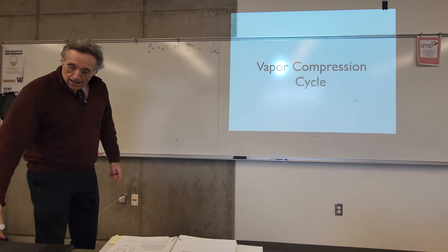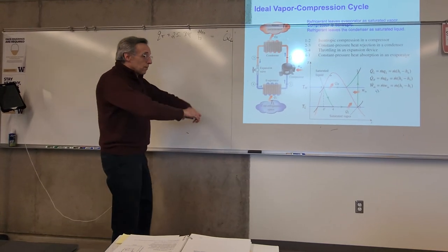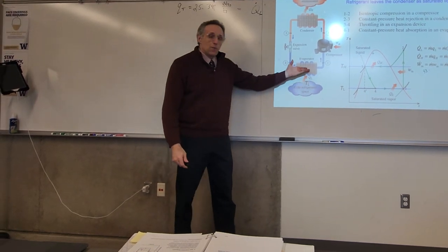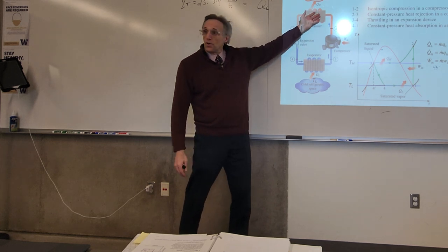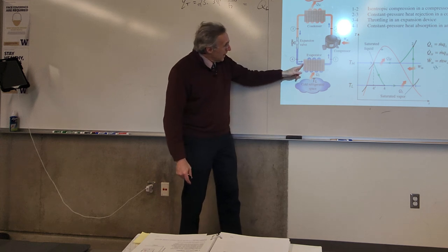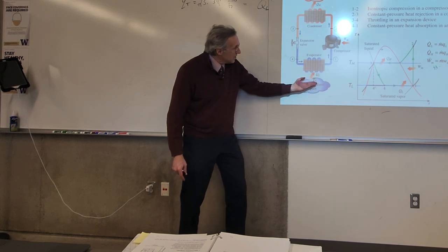And if we look at vapor compression, you open up the black box in the middle of that diagram we just saw, and this is what it looks like. This is the cooling coil. It's an evaporator, but in HVAC we often refer to it as the cooling coil. If we're using a heat pump for heating, then the condenser will be the source of our heat. So this would be the heating coil in winter, cooling coil in summer. The refrigerant enters as liquid or a liquid-vapor mixture, and then it evaporates at constant temperature and constant pressure.